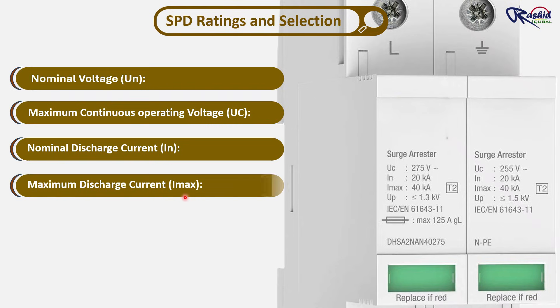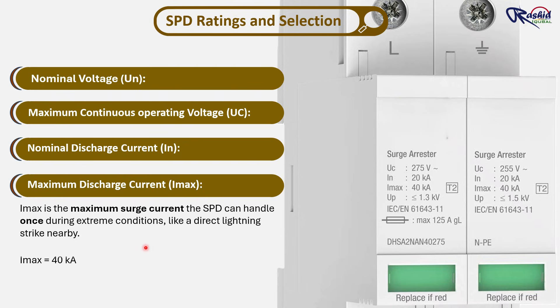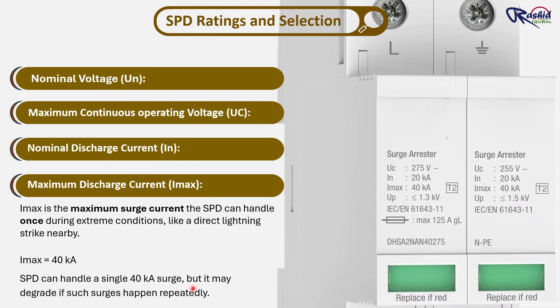Number 4 is maximum discharge current, IMAX. IMAX is the maximum surge current the SPD can handle once during extreme conditions, like a direct lightning strike nearby. For example, if IMAX is 40kA, then the SPD can handle a single 40kA surge one time. But it may degrade or be damaged if such surges happen repeatedly.